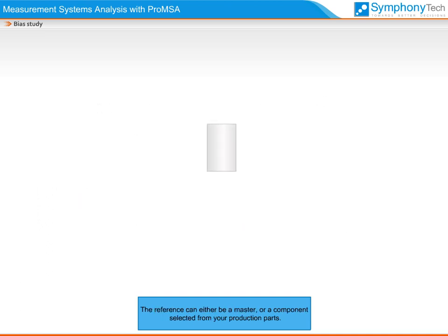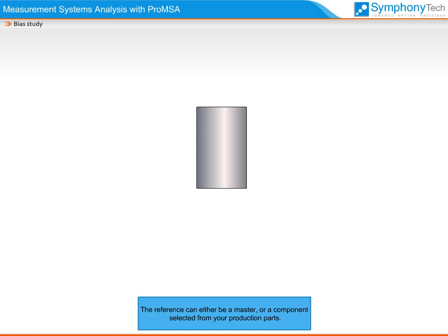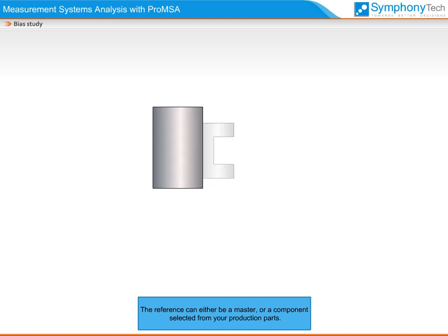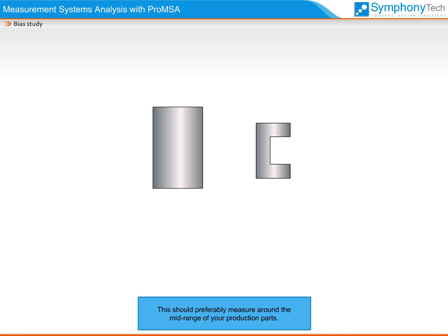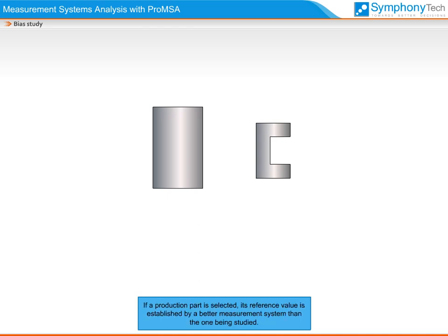The reference can either be a master or a component selected from your production parts. This should preferably measure around the mid-range of your production parts. If a production part is selected, its reference value is established by a better measurement system than the one being studied.